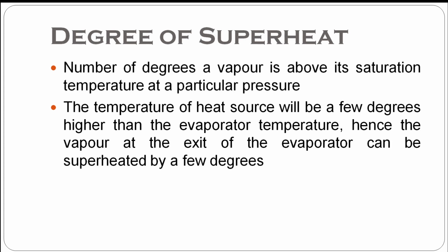The temperature of the heat source will be a few degrees higher than the evaporator temperature. Hence, the vapor at the exit of the evaporator can be superheated by a few degrees, so that the entire refrigerant entering the compressor will be in the vapor form. In order to ensure only vapor refrigerant in the compressor, we maintain a constant degree of superheat. We have seen this in the discussion on expansion devices, right? A particular type of expansion device is used, the thermostatic expansion valve, so that a degree of superheat is always maintained.